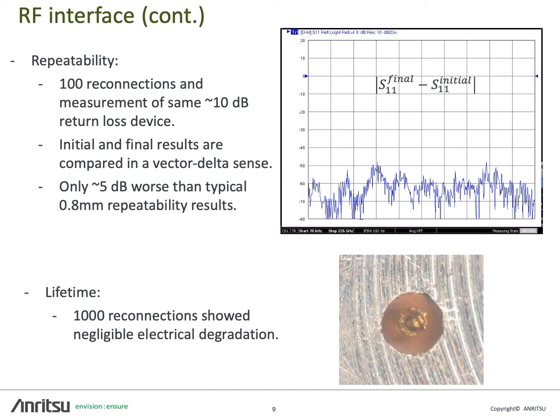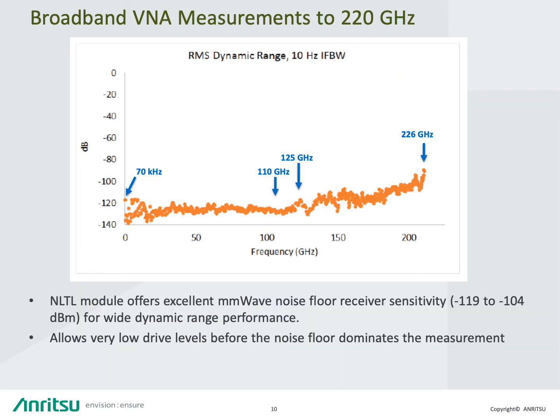In this plot we're showing the vector delta comparisons between initial and final results over 100 connections of a return loss device of about 10 dB, and you can see that at 50 dB it's providing very good repeatability and on par with the 0.8 threaded connector. So the overall system performance then is broadband measurements to 220 gigahertz with very good dynamic range and no sacrifice in performance at 110 gigahertz.